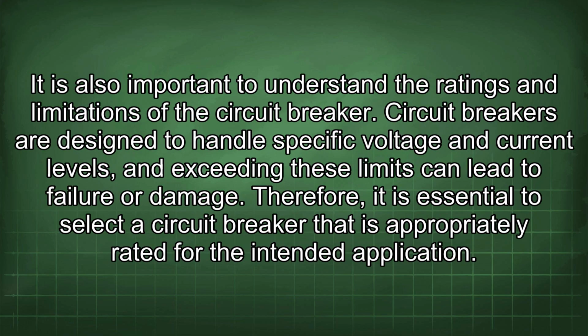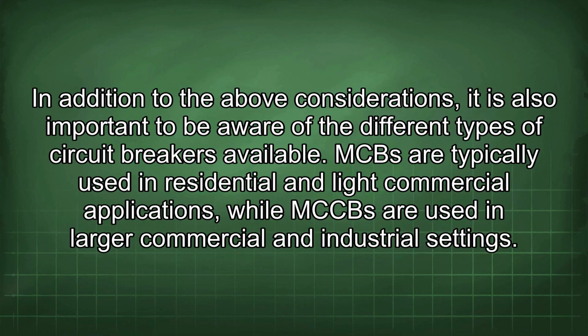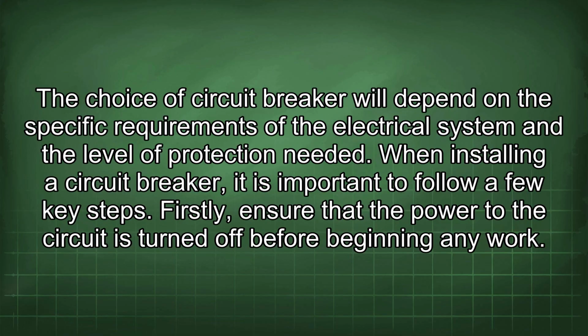It is also important to understand the ratings and limitations of the circuit breaker. Circuit breakers are designed to handle specific voltage and current levels, and exceeding these limits can lead to failure or damage. Therefore, it is essential to select a circuit breaker that is appropriately rated for the intended application. In addition, it is important to be aware of the different types of circuit breakers available. MCBs are typically used in residential and light commercial applications, while MCCBs are used in larger commercial and industrial settings. The choice of circuit breaker will depend on the specific requirements of the electrical system and the level of protection needed.